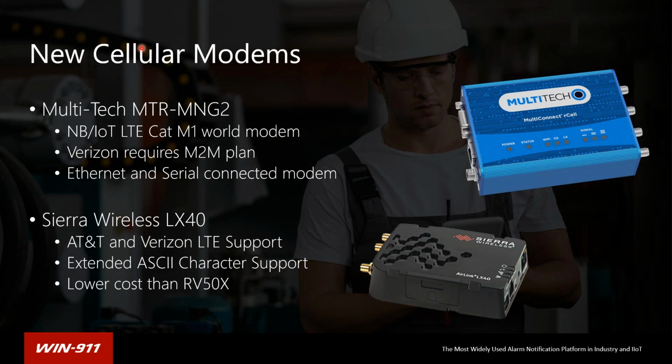So recently, Multitech has released a new modem, which is their MNG2. It is an IoT or narrowband modem. It's not the same as the existing modem, so it's still a Telit chipset, but it works on a different technology. And the reason I point that out is because if you want to get this modem and use it with Verizon, you can't go through your normal Verizon account. If any of you have commissioned any IoT equipment with Verizon, then you probably know this already. So you'll have to go to Verizon, set up a new account with an M2M plan or machine-to-machine plan, IoT plan, whatever they're calling it today, and get special SIM cards for it to use that modem. If you're using AT&T, then you can just put a regular SIM card in there and it will work.